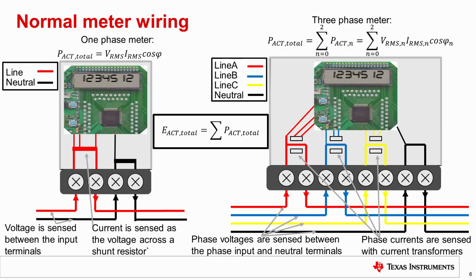corresponds to neutral out. In this configuration, the energy consumption is calculated by measuring the voltage between line in and neutral in and the current sensed across a shunt connected between line in and line out. The sum of the voltage-current product is used to calculate the active power. This is also equivalent to the product of the RMS voltage and RMS current multiplied by the cosine of the angle between the voltage and current.